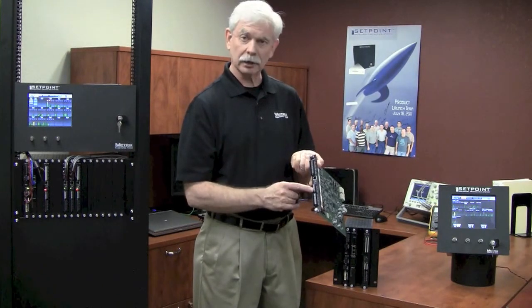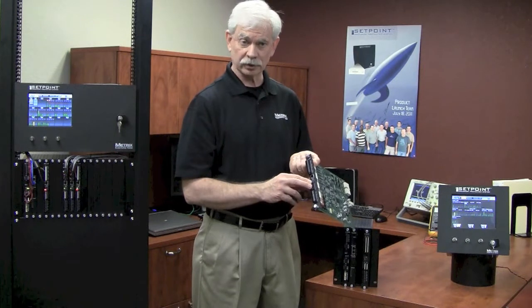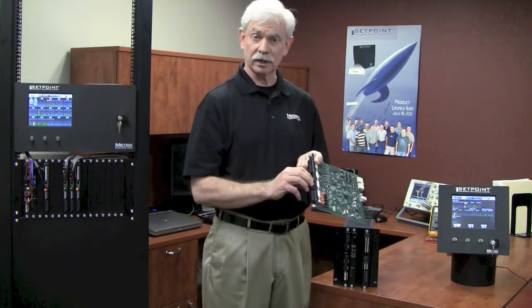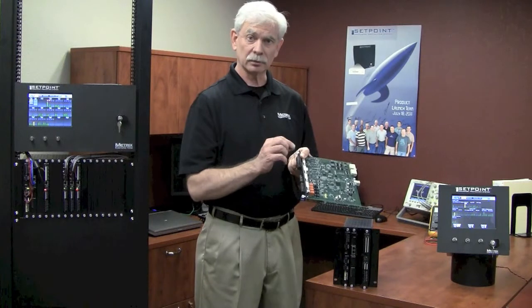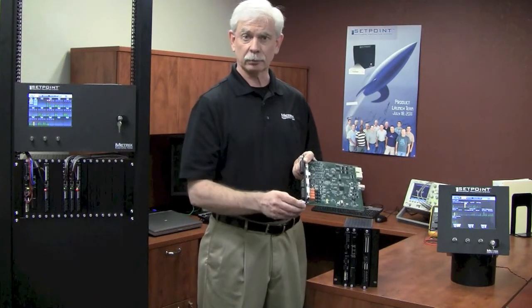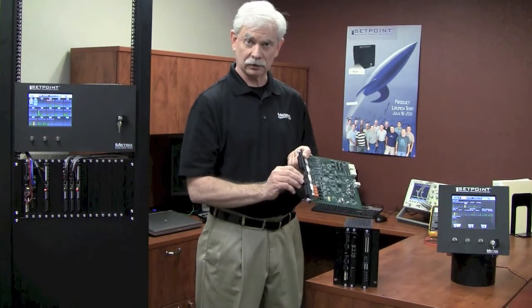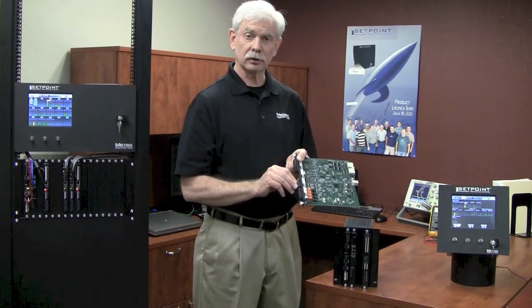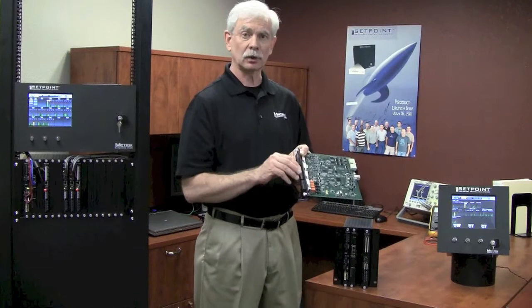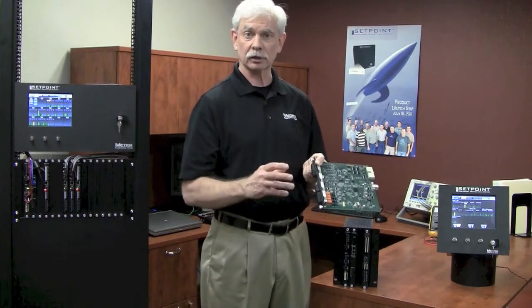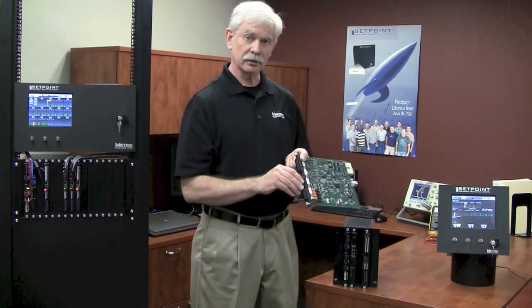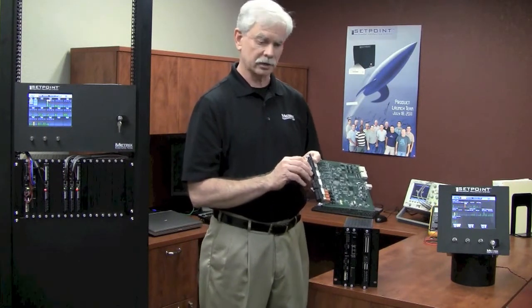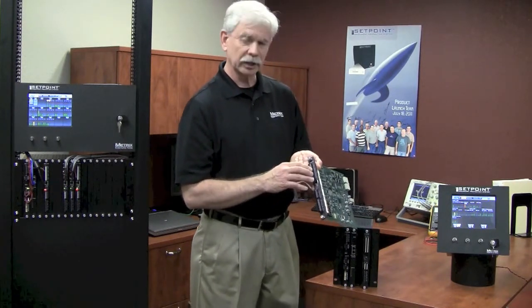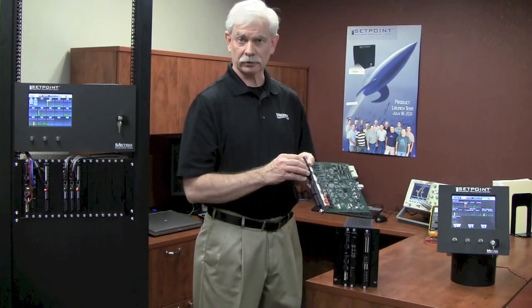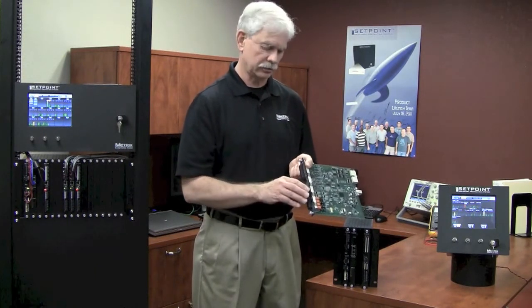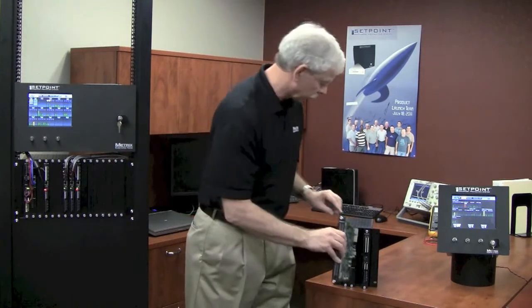It has four analog outputs for 4 to 20 milliamp type signals, and those are programmable, by the way, so not only can you decide you want to put direct or 1x filtered vibration or gap voltage out on the analog outputs, but you can also assign gap voltage from channel 1 and overall amplitude from channel 2. There's a lot of flexibility in how those analog outputs can be used in our configuration software. And then, of course, at the top, we have our connector for the power out to the transducers and the signal in from the transducers. So that is a four-channel universal monitoring module.